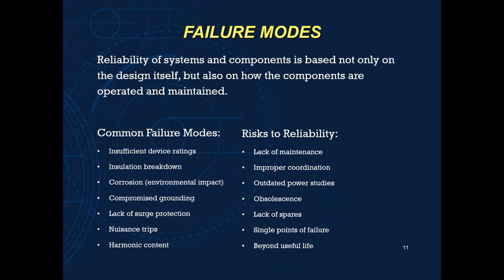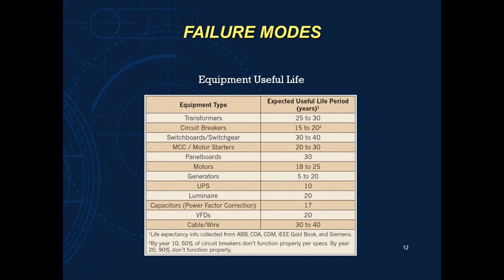You have a lot of other things that I call risks to reliability. While reliability might be something concrete and calculated, lack of maintenance, for instance, will cause premature failure of a component. If you're not coordinated with your protection components and your components don't operate in the correct order, you can take outages that were not intended to clear a fault that's on one component. There's a lot of different things that go into reliability that we can measure, and then there's things that we cannot measure.